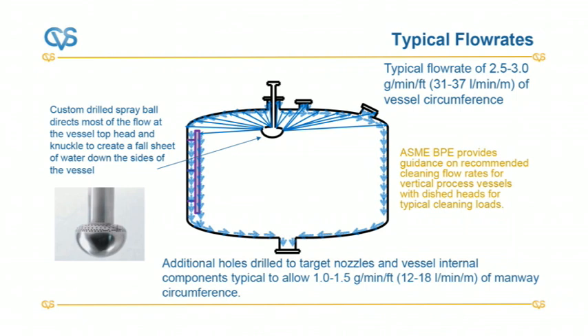And that's out of the ASME BPE. I think it's the 2009 guide. There's a little bit more in the later versions. Now, the ASME BPE does give you some examples of flow rates. So here's our vessel, and this is our static spray ball. We've got purpose-built holes drilled to spray various parts of the upper surface. Custom drilled means it's been drilled specifically to direct water or cleaning fluid to certain points in there.